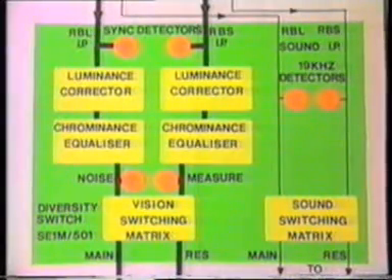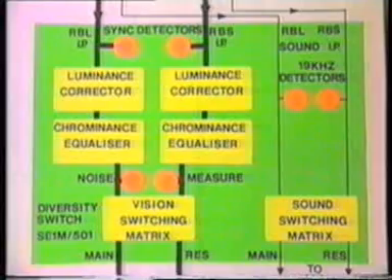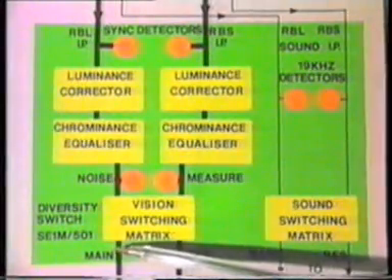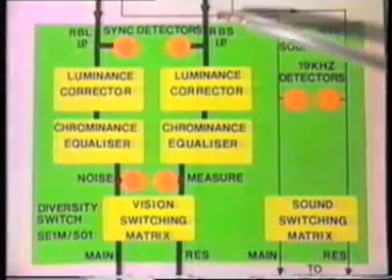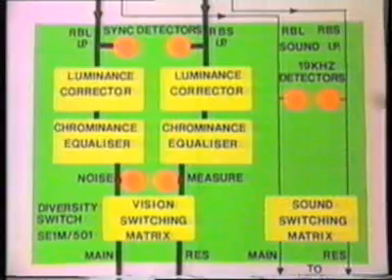As the diversity switch is bypassed, there'll be no program passing through it, and the AFR will send out three alarms: receiver A fail, receiver B fail, and diversity fail. It's easy to think, on seeing these indications, that there's a loss of program. So remember that the receiver indications are derived from the diversity switch. Diversity fail will automatically produce the two receiver fail alarms.